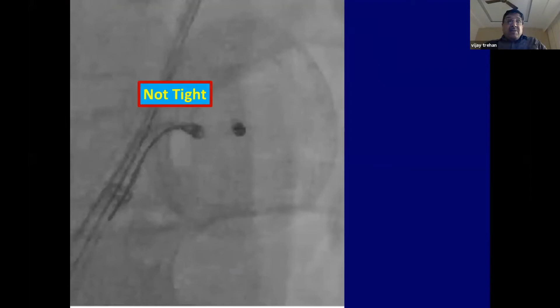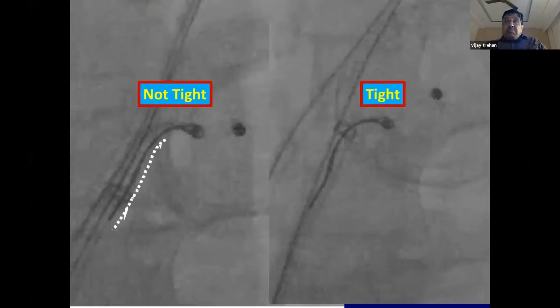So that is what we were with the device, and my colleague was quick to catch the device, but was not able to get it into the sheath. Probably he was not catching it tight. And how do you know you're catching it tight or not? I think just pay attention to this part of the loop of the snare within your snare catheter. If you catch it well, this straight part will bend. It will never be straight if you're tight.